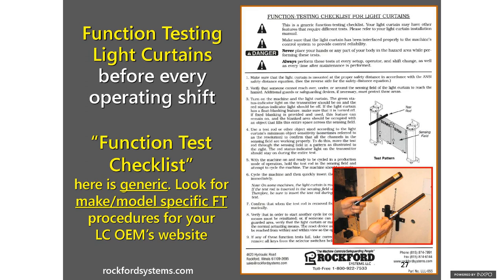So function testing light curtains needs to be a make and model specific procedure, which this one is not. If you can read that top line, that's a generic procedure. So why have a generic procedure if every light curtain manufacturer has their own individual make and model specific function test procedure? Well, the reason is some of the light curtain manufacturers are no longer around. So you have to start with something in making your own function test procedure. But wherever possible, go to the light curtain manufacturer, go on their website, look for function test procedures, as well as those black rods in the lower right corner. Those are test rods that are used as part of the function test procedure and must be a very specific diameter. Both the fat one and the skinny one have to be a specific diameter to make this work.